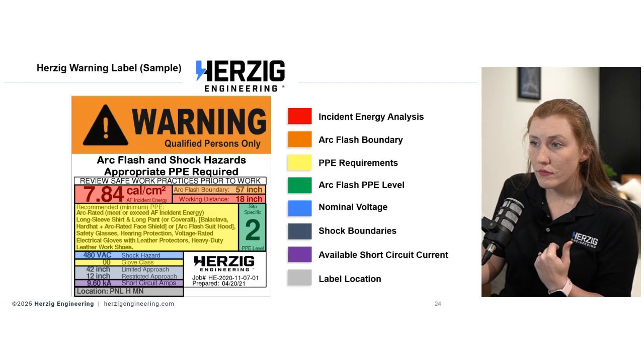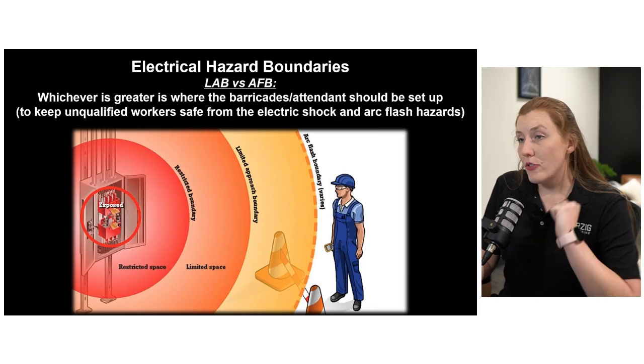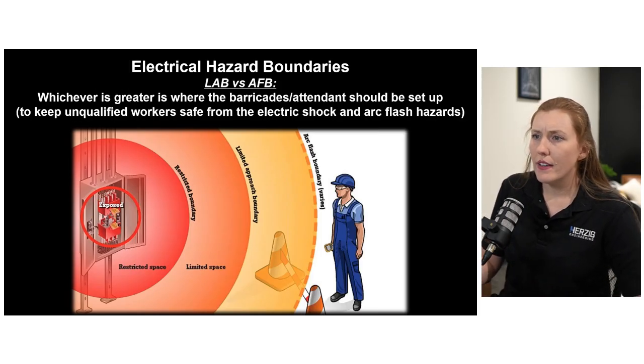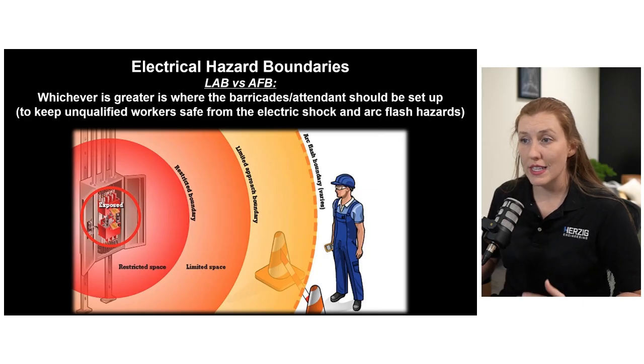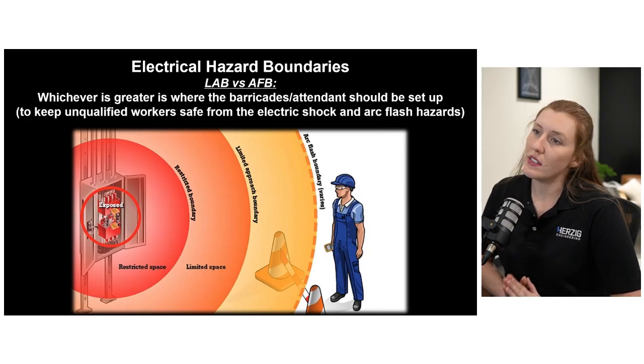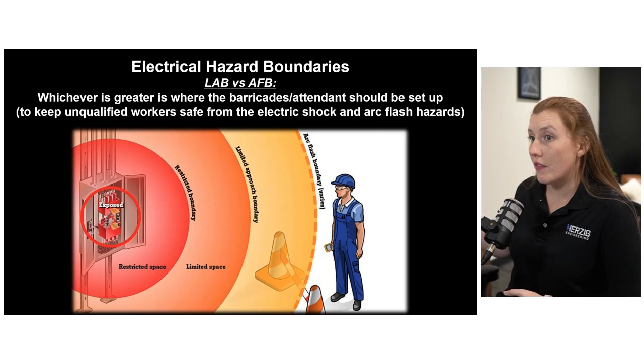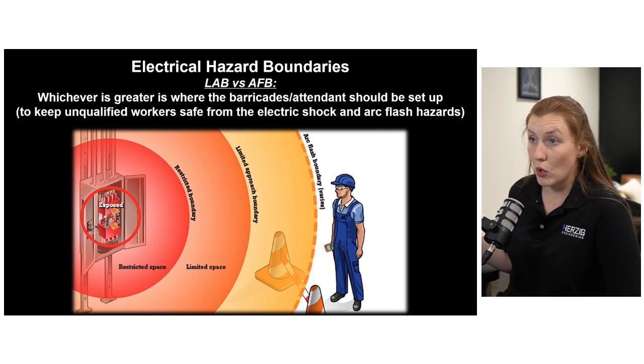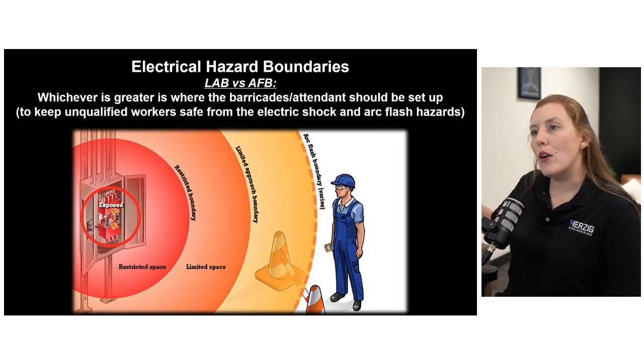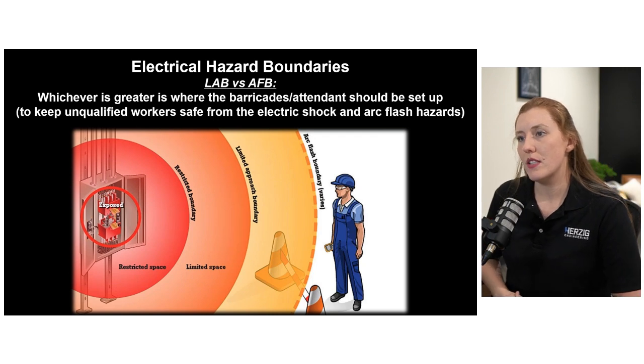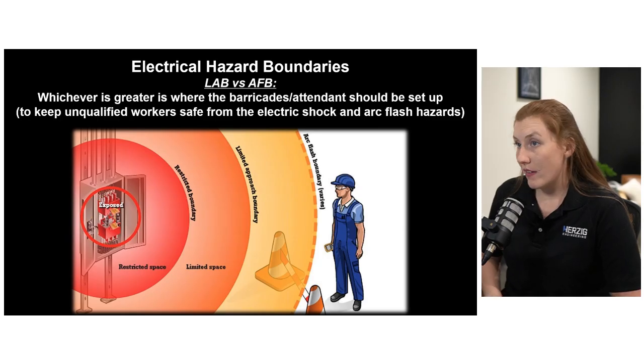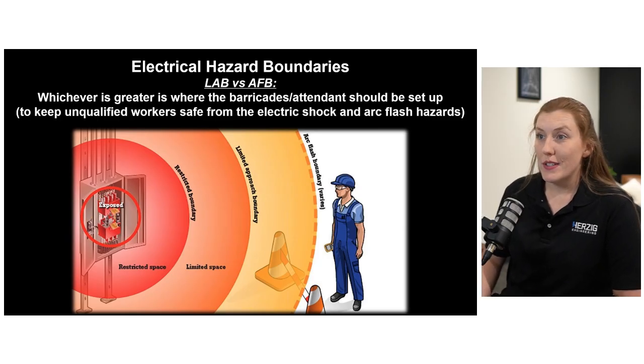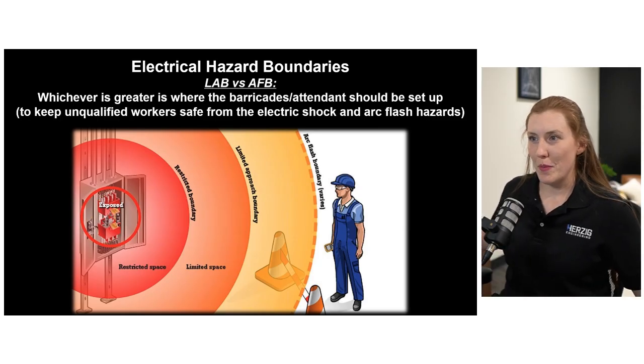For the boundaries, reinforcing that - wherever the furthest boundary is, that's the bare minimum you have to set up your work area to keep unqualified, or honestly even qualified people who aren't protected, outside of those boundaries. The moment you cross the boundary, if it's exposed, you have to have your protective equipment on. So establish the boundaries first and foremost.